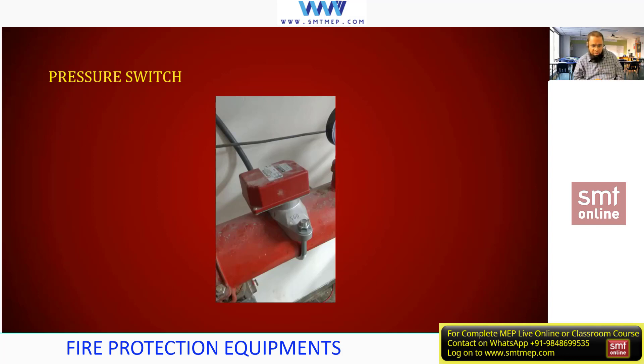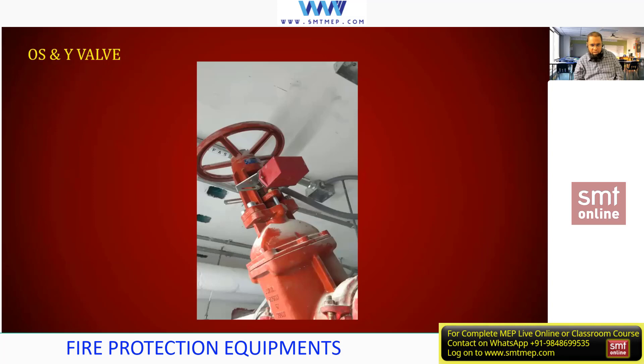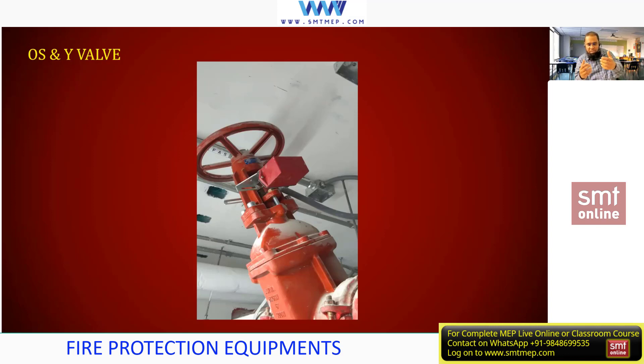Now a closer view of the OS&Y gate valve. OS&Y means Outside Screw and Yoke - it's a gate valve, a normal gate valve, but in firefighting we use the OS&Y gate valve because the outside yoke and screw give you the advantage that from the outside, just by visual inspection, you can check whether it is in the open or closed position. I'll explain exactly how when we have a separate topic for the zone control valve assembly.